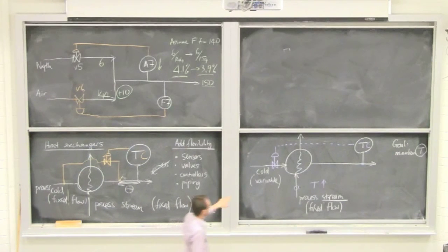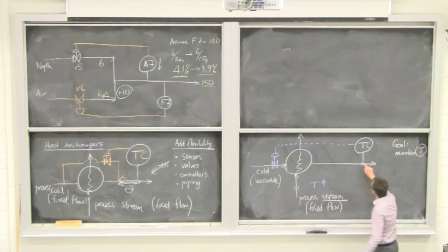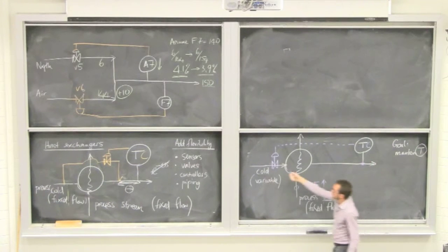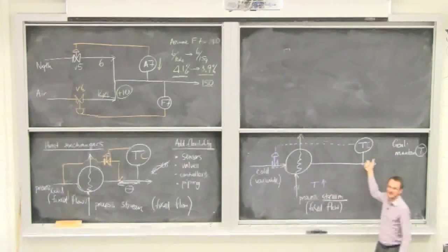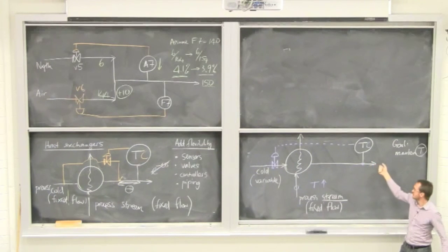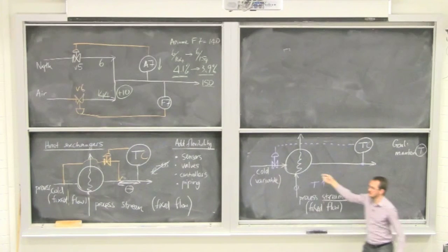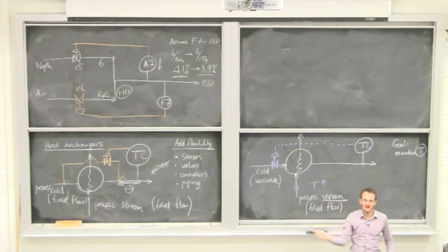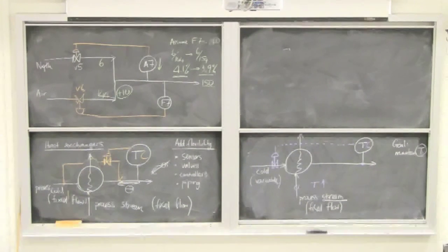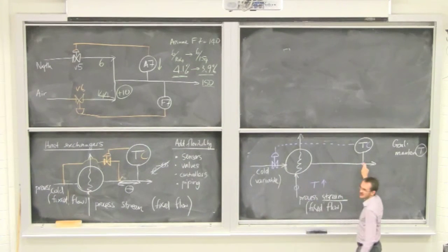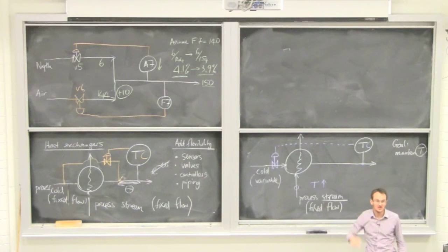If you take a look at this diagram, if we make a change here in the flow, what is the time before we see it here at the sensor? What are the restrictions in our path? The heat exchanger, right? And a heat exchanger, we've got these banks and banks of tubes in hairpin shapes. So the time taken for a change here in the valve before you see it at the sensor is actually longer. So this bypass configuration is a lot more responsive.